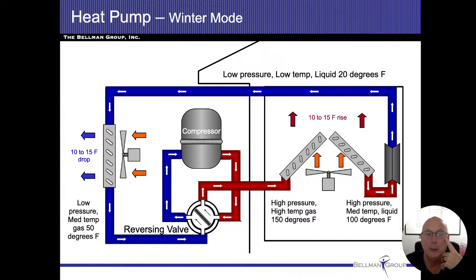And we don't want to put heat pumps on, what do you call those, setback thermostats where we change the temperature a lot, like a Nest where we'll lower the temperature or let it heat up in the house when we're at work. And then all of a sudden, about a half hour before we come home, we turn it on and expect everything to drop. It doesn't work well that way. Heat pumps, when they're working for heat, we want it to stay consistent. All right. We want them to be on and maintain a steady temperature. That's when they work best.